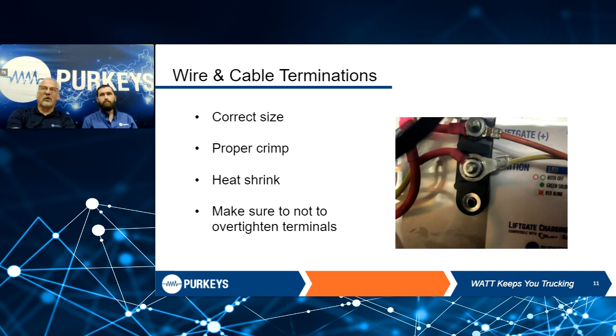So you got to make sure we're matched for that, because that will create heat resistance, maybe a hot spot. Anytime I have warm wire or connections getting warm, there's more resistance there. Once again, I can't get the current flow out there that I should be getting to the components.